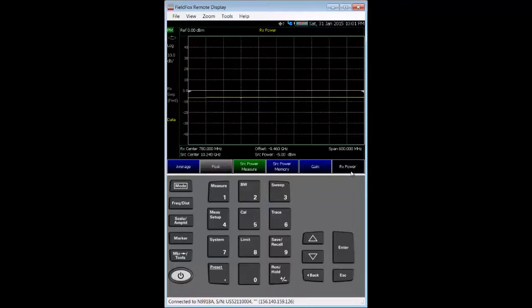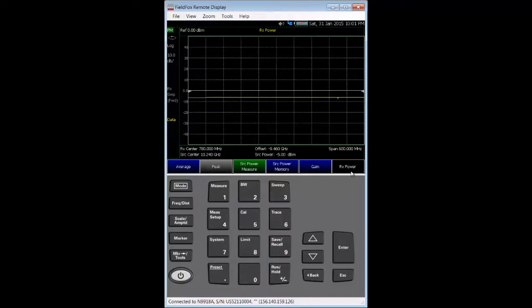After the calibration, the measurement reference plane is established. Now, I will reconnect port one and the USB power sensor to the frequency converter's RF and IF ports.